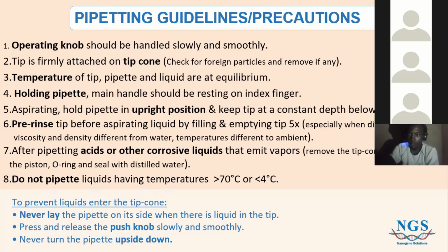I would say yes. I think it would be wise to calibrate your pipette even if only one value is not in range, because as you saw in the table from before, the range is actually very large. When professionals are calibrating the pipette, they will calibrate it in a way that every volume is in range.